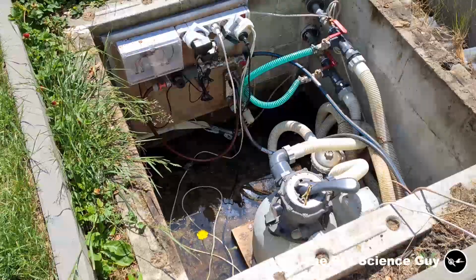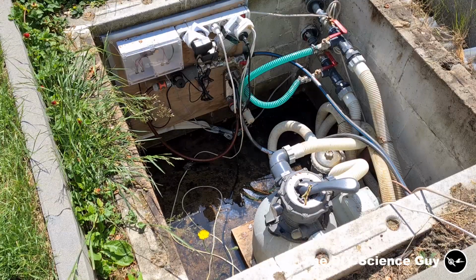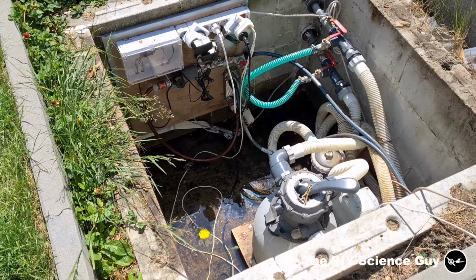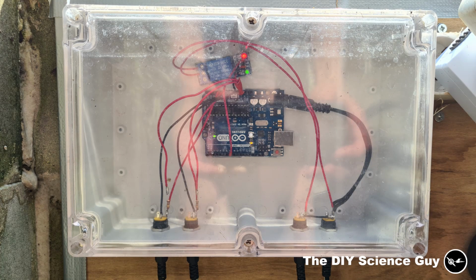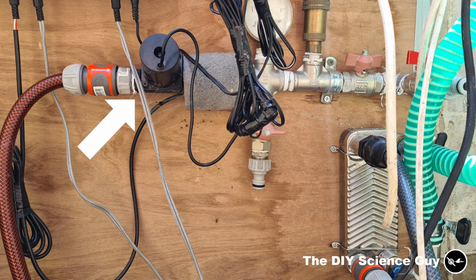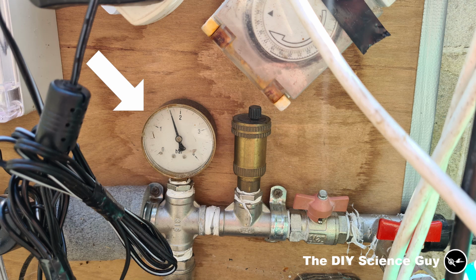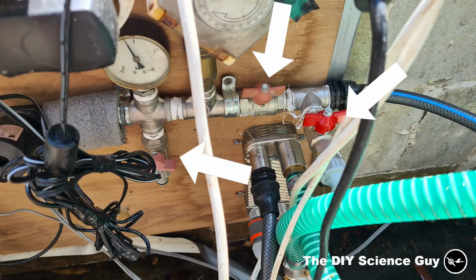Okay, so now to the actual setup. This is how I've set it up now in this hot tub filter pit. This is the Arduino housing, the panel circulation pump, the insulated temperature sensor that measures the panel circuit temperature, a pressure gauge, an automatic air vent, and some valves and couplings to fill the system.